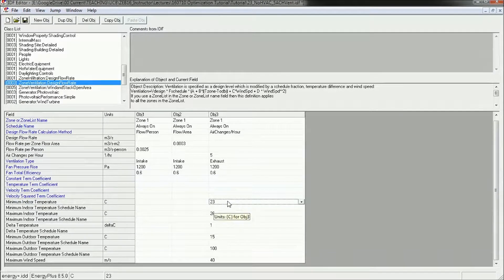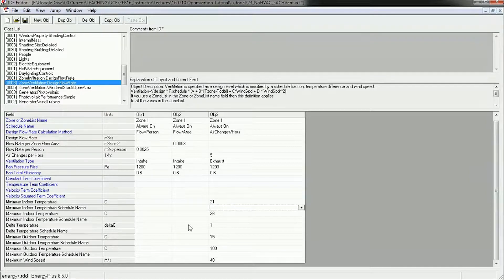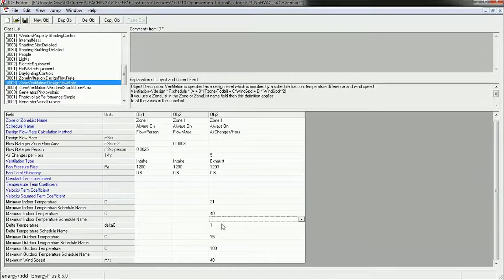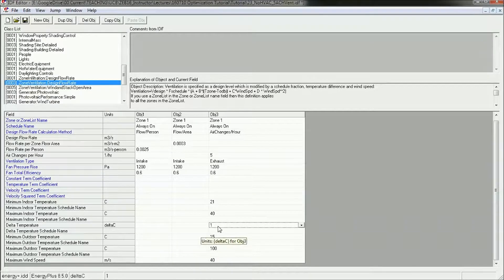You want to set the minimum indoor temperature to be something reasonable for that climate. 23 degrees is probably okay for Miami — it could even be lower, maybe 22 or 21. I'm going to go with 21 for this. The maximum indoor temperature — for Miami I'm going to jack this way up to 40 degrees Celsius so I make sure that fan is always on. The minimum outdoor temperature I'm going to keep at 15 degrees, and the delta temperature at 1 degree.